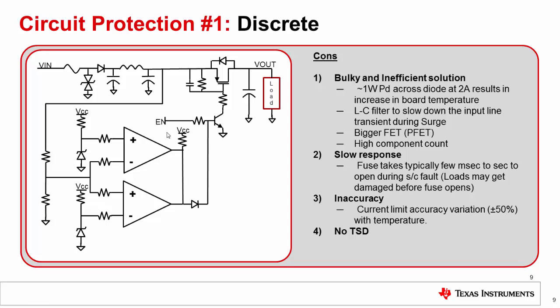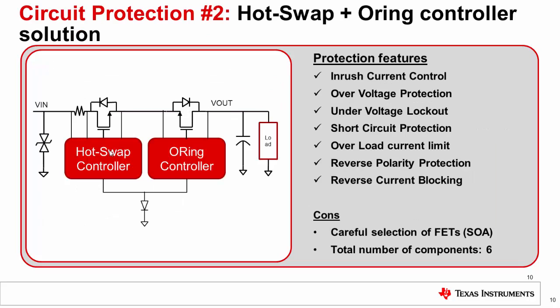This circuit also does not have a thermal shutdown feature. Here we show a semi-discrete solution based on a hot-swap and ORing controller with an external FET and a current sense resistor. The protection features include inrush current control, over-voltage protection, under-voltage protection, output short circuit protection, overload current limit, reverse polarity protection, and reverse current blocking. A careful selection of FETs is needed when designing these circuits.